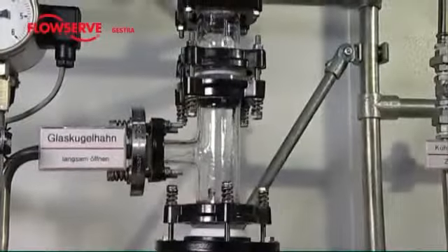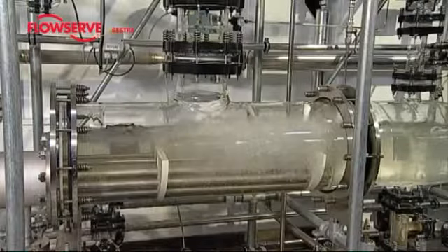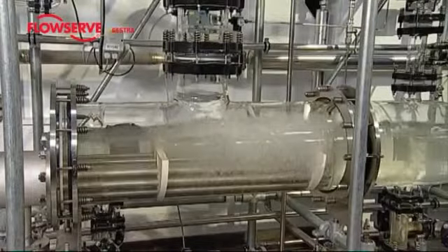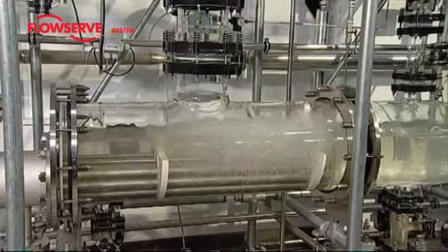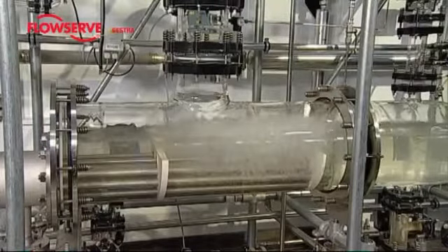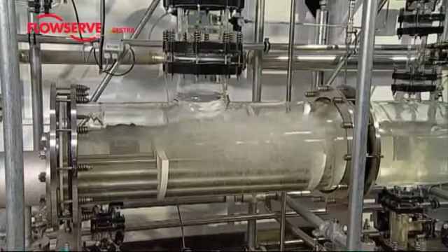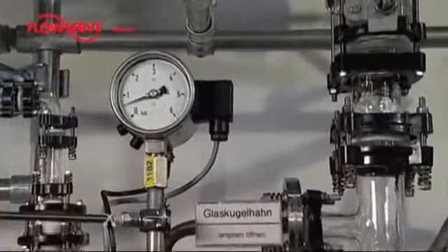We will now conduct a test by increasing the level of the water in the steam boiler from 60 to 67%. Slowly, the feed water valve opens, and feed water with a lower temperature than that of the boiler water enters the steam boiler. This now mixes with the boiler water. Because the temperature of the mixture lies below the boiling point, there's no longer any formation of steam bubbles in this area. The steam boiler lacks performance, and a glance at the pressure gauge tells us that the working pressure is sinking.